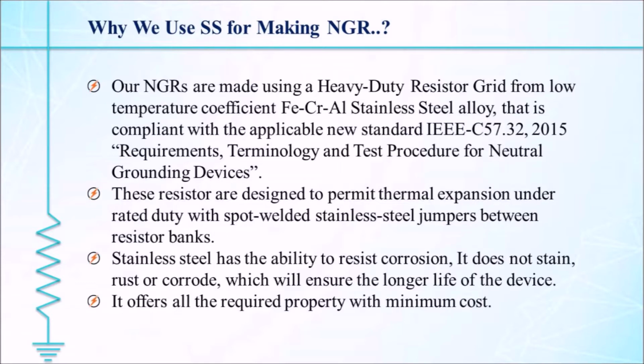Stainless steel is the material which obeys all the norms designed by IEEE for grounding devices. It is an alloy made up of a mixture of carbon, chromium, nickel and molybdenum, which belongs to the highly corrosion resistive family. Hence it does not corrode or rust and ensures a longer life of the device. It has a positive temperature coefficient of resistance, which means with an increase in temperature, resistance also increases, which will help us suppress heavy fault current and serve the purpose of NGR.